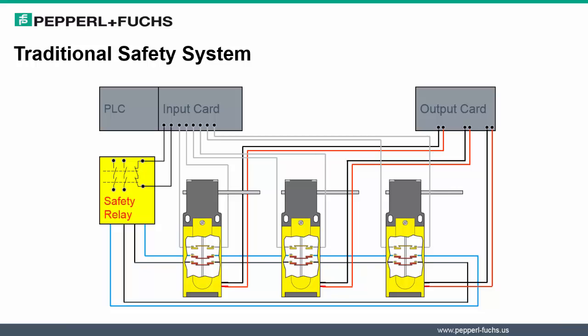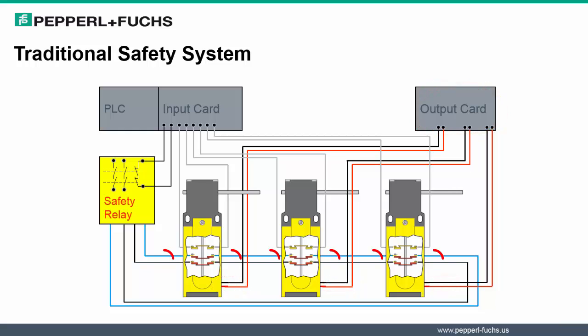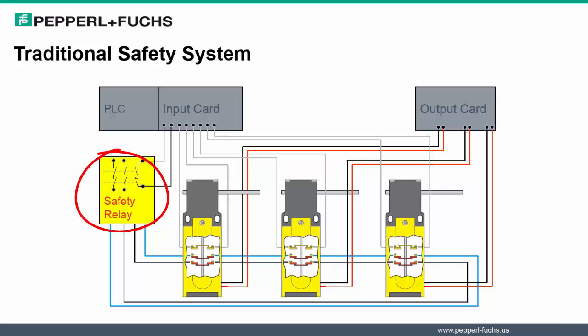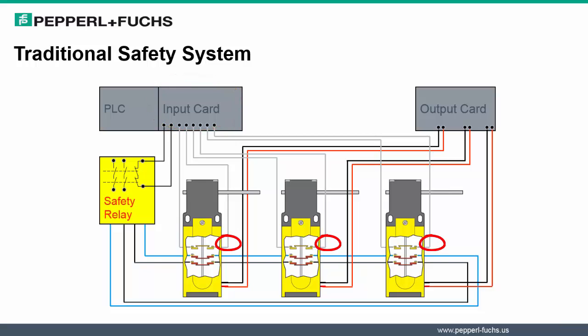Now let's look at a typical arrangement of a traditional safety system. First, solenoid locking inputs had to be routed to output cards of the PLC. Secondly, the redundant safety contacts were daisy-chained to each other and connected to an external safety relay, which connected to a PLC input card. Finally, auxiliary contacts had to be routed to input cards of the PLC. After putting such a system together, it became evident very quickly that numerous manual connections were needed. Long conduit and cable runs had to be made, and complex wiring was unavoidable.